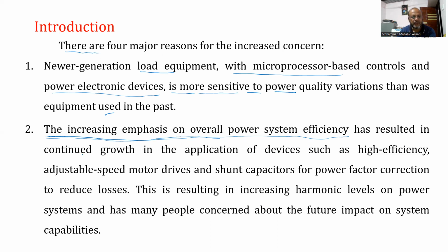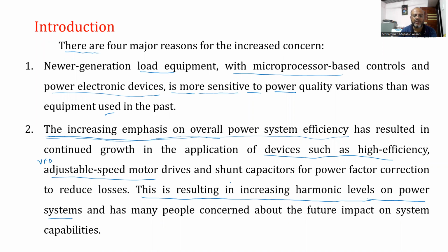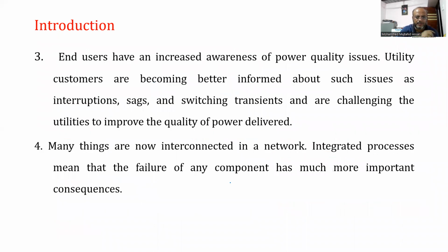That has resulted in growth in the application of devices such as high efficiency adjustable speed motors, instead of using gear drives, which lead to more power losses. We are using variable frequency drives or adjustable drives, and these adjustable drives definitely produce harmonics in the system. So this results in increasing harmonic levels on the power system. No doubt we are increasing the efficiency of the system, but at the same time the power system gets polluted. That pollution is nothing but the harmonics.